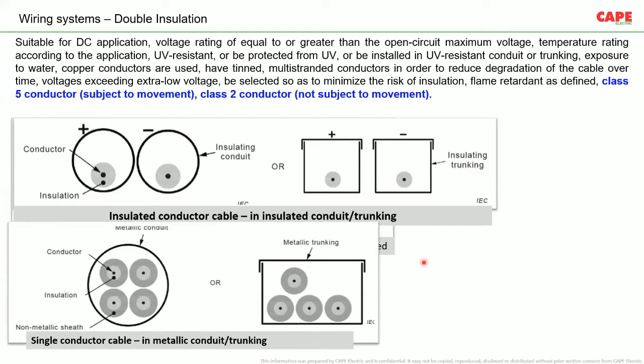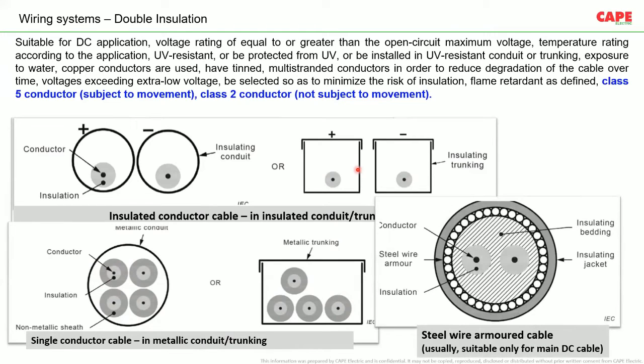If you are using metallic trunking, the wires must be double insulated. You see here a metallic conduit, and inside the metallic conduit, the wires are double insulated. So all these wires are double insulated, another metallic trunking with a double insulated wire. So this means a normal wire inside metallic trunking is a violation of the rule for class 2 installation. So you cannot do it. Different methods of achieving double insulation are explained in the standard. I request you please go through the standard, understand it, and try to implement.